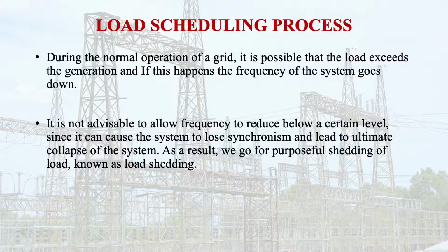The standard frequency is 50 Hz, but the frequency can go down up to 49 Hz. After this value, it is not advisable to allow it to reduce any further, since it can cause the system to lose synchronism and lead to ultimate collapse of the system. So as a result, we go for purposeful shedding of the load, which is known as load shedding. That means purposeful power cut. So this is called load shedding.